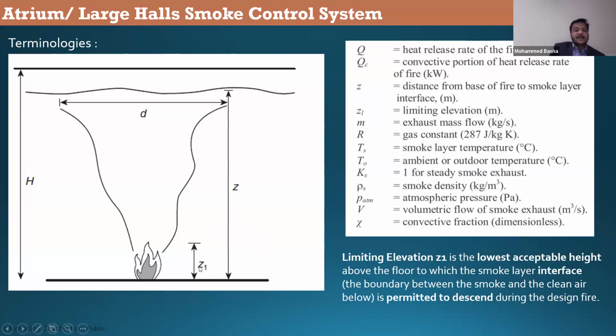Z1 is called limiting elevation, which we will not consider much, but I will explain what that is. Limiting elevation is the lowest acceptable height above the floor to which the smoke layer interface can descend. But Z1 will sometimes be higher. But if you can maintain Z, which is the clear interface height, you will be complying with Z1 as well. And there are certain fundamentals also to understand.